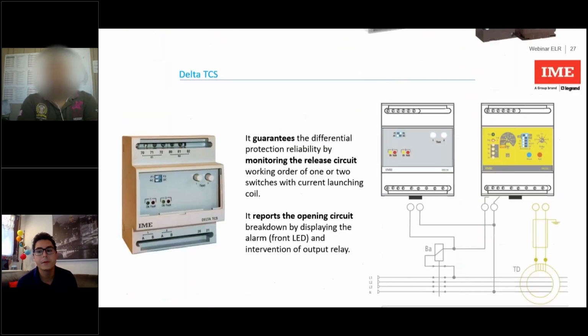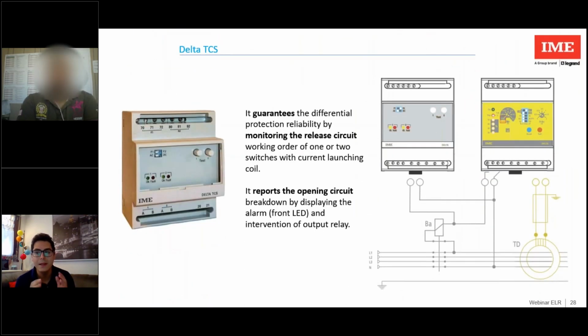Well, a mention was also made of the release monitor, called Delta TCS. This device monitors the trip circuit of 1 or 2 relays and reports an alarm if it finds a disconnected or non-functioning current release coil.